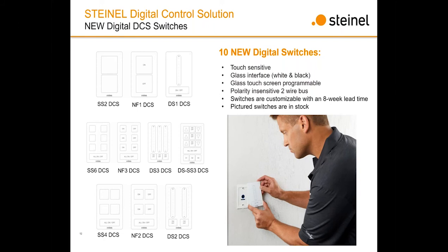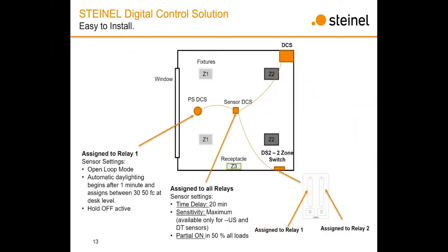Installation, again, is super simple, but the best part about installing with the DCS is that there are many situations where it functions right out of the box and you do not need a tech or anyone to come and commission it. So, for example, what you see here on the screen: we have a single DCS with 3 zones in a room, 2 zones of fixtures, and a DS2, which is the 2-zone switch. Right out of the box, the DCS assigns relays 1 and 2 to the 2-zone wall switch, so zones 1 and 2 of the fixtures now function with this wall switch. The DCS sensor gets assigned to zones 1, 2, and 3 with a time delay of 20 minutes, partial on to 50% of the loads. And then the photo cell gets automatically assigned to zone 1 in an open loop mode. So this entire room, right out of the box, without having a tech come to site, all you do is plug it in, and it functions and is code compliant.